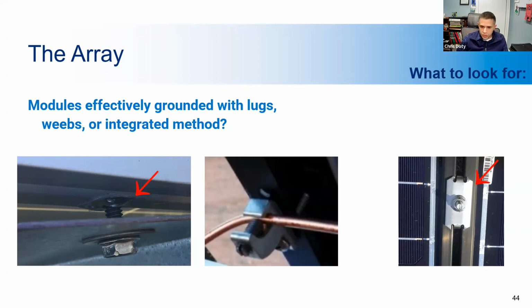Many of the newer arrays use this kind of bonding. And you can see over here, you want to make sure that everything is installed in a nice tight manner. This has a screw coming out, which obviously you want to avoid. You want to make sure everything is nice and tight. And in the middle, you can see an example of a ground lug, which is another grounding method you might see. It's becoming less popular than the integrated bonding, but you will still see it.